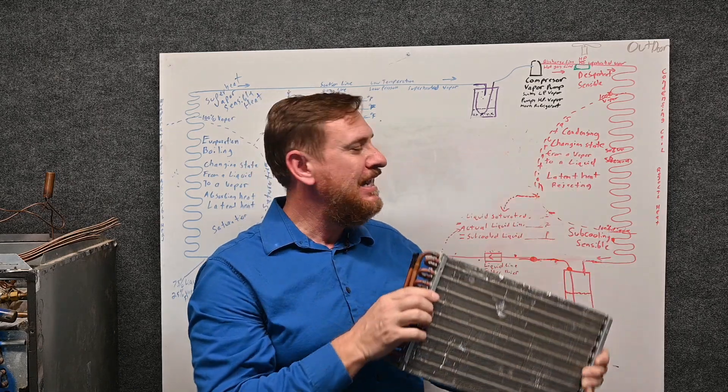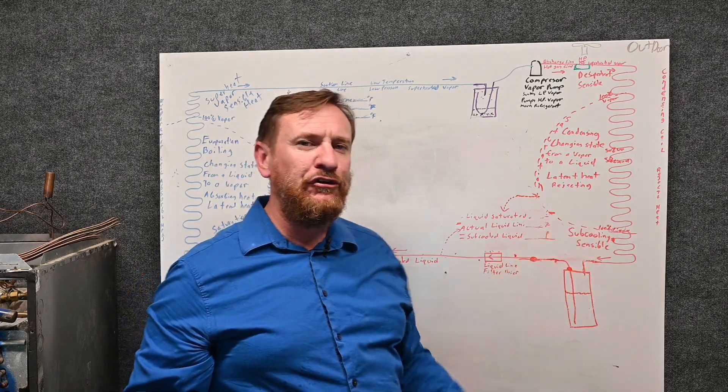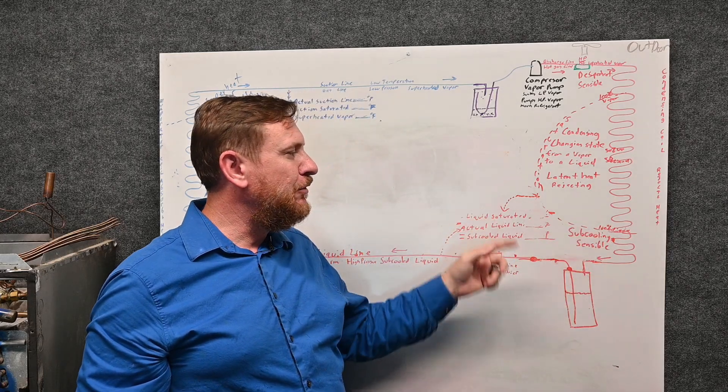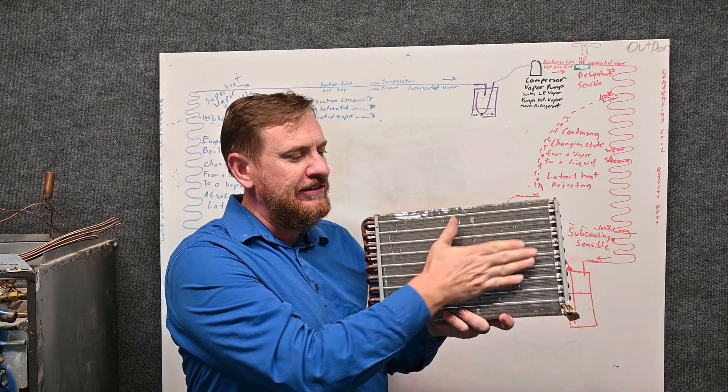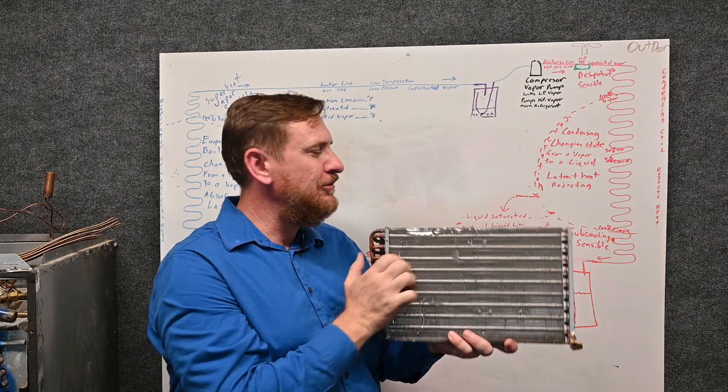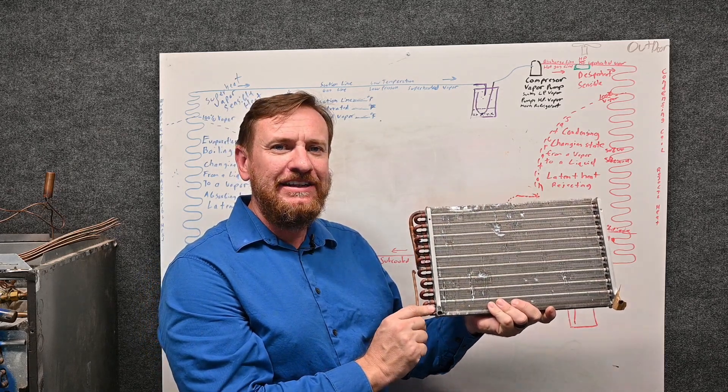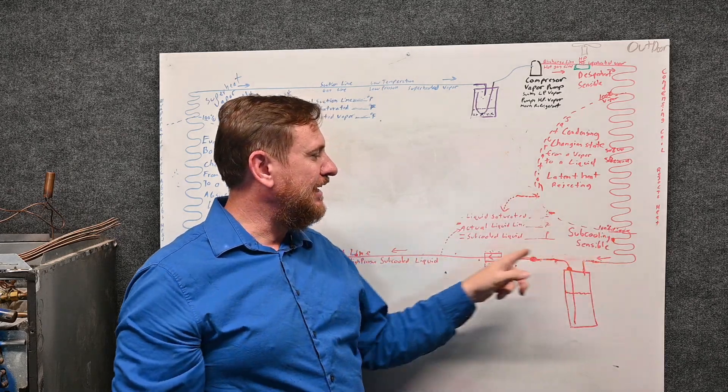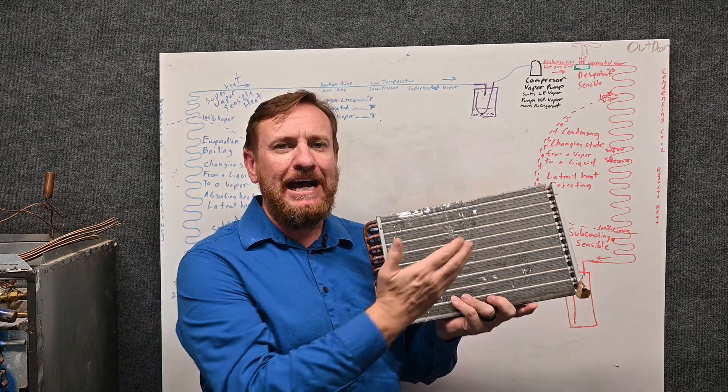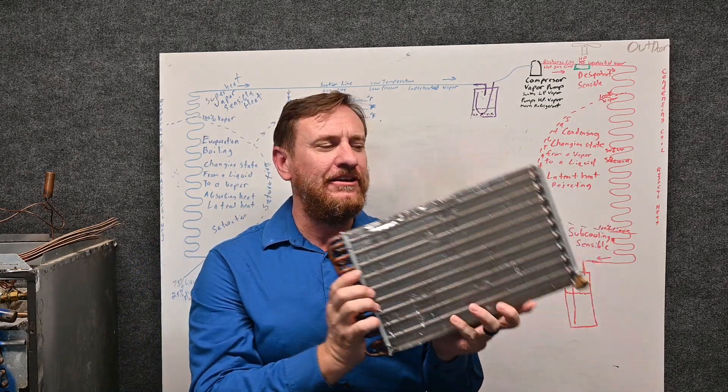That's where our formula for subcooling comes in: the liquid saturated temperature, which is taking place approximately here—PSIG converted to temperature—minus my actual liquid line temperature. So the line leaving the condenser, the actual liquid line, equals our subcool liquid—how much subcooling, how much sensible heat we've taken out of this condenser.